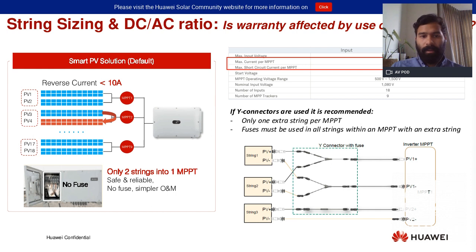As I was saying, here with the Y connectors, you can do it. And also, a very common question is if the warranty of the inverter is going to be affected. The answer is no. You can use Y connector, and this will not invalidate the warranty.